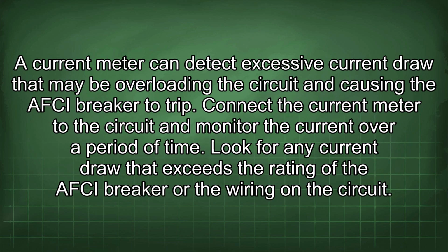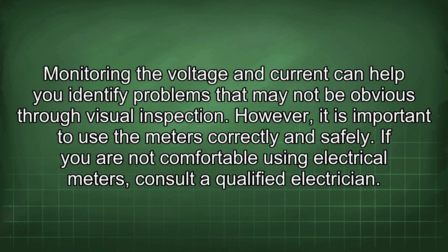A current meter can detect excessive current draw that may be overloading the circuit and causing the AFCI breaker to trip. Connect the current meter to the circuit and monitor the current over a period of time. Look for any current draw that exceeds the rating of the AFCI breaker or the wiring on the circuit. Monitoring the voltage and current can help you identify problems that may not be obvious through visual inspection. However, it is important to use the meters correctly and safely. If you are not comfortable using electrical meters, consult a qualified electrician.